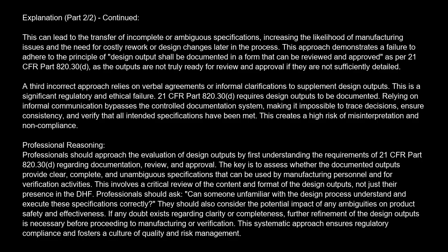This approach demonstrates a failure to adhere to the principle that design output shall be documented in a form that can be reviewed and approved, as per 21 CFR Part 820.30(d), as the outputs are not truly ready for review and approval if they are not sufficiently detailed.